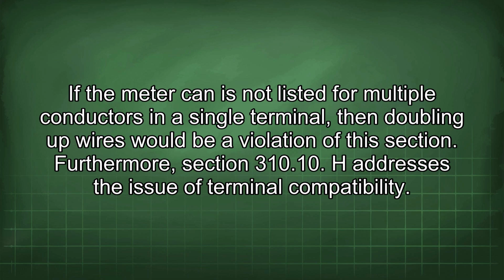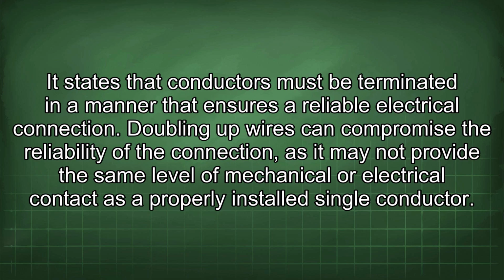Furthermore, Section 310.10(H) addresses the issue of terminal compatibility. It states that conductors must be terminated in a manner that ensures a reliable electrical connection. Doubling up wires can compromise the reliability of the connection, as it may not provide the same level of mechanical or electrical contact as a properly installed single conductor.